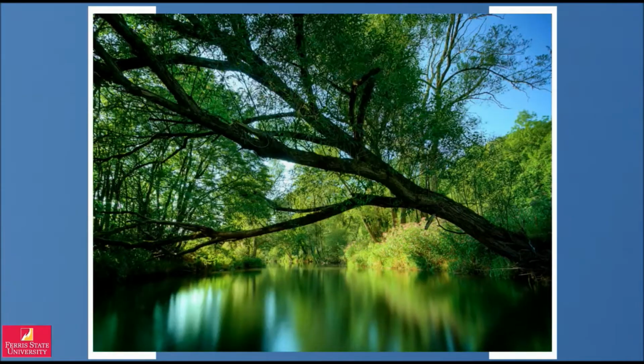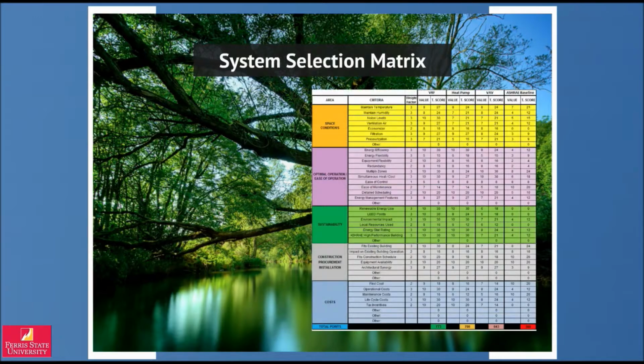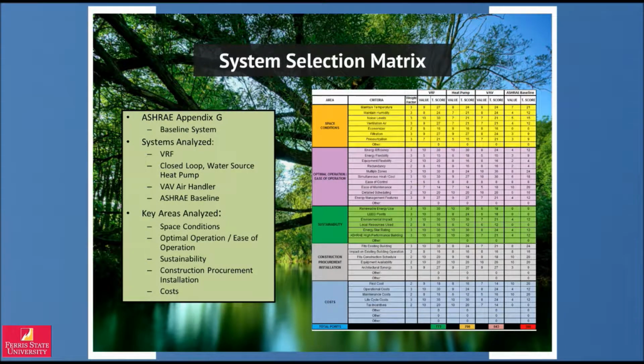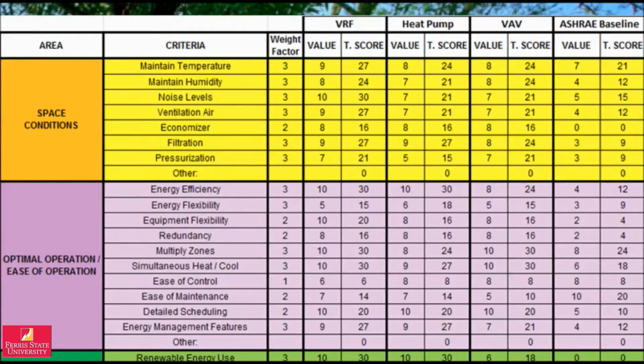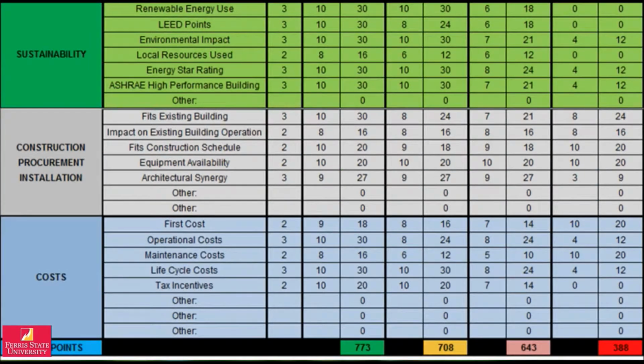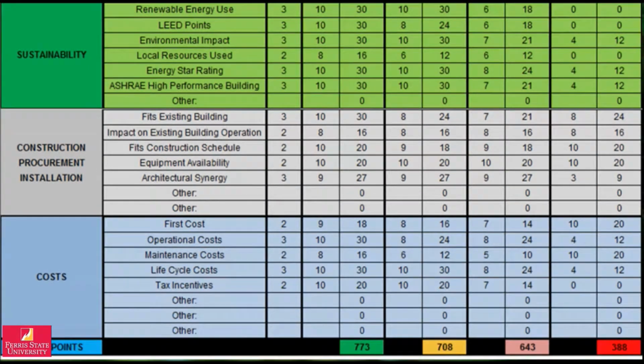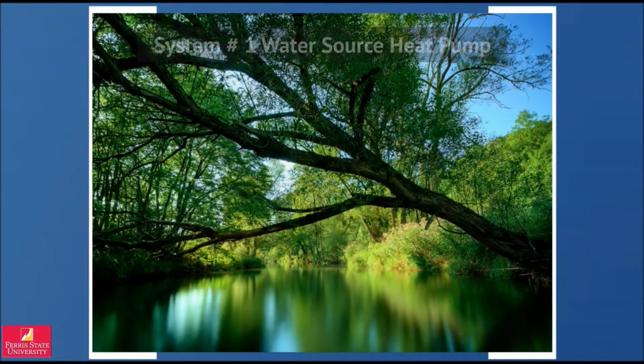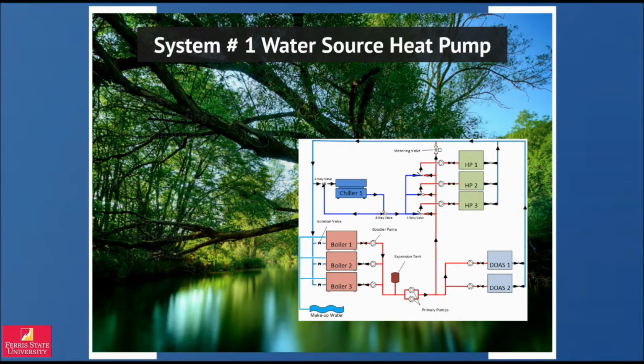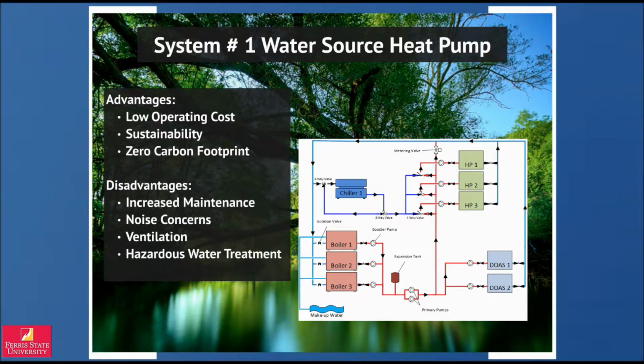From there, 3 HVAC systems were selected for comparison against the ASHRAE Appendix G baseline system through the use of a selection matrix. The 5 core areas of concern were assigned a point value with a weight factor emphasizing the importance of key criteria of each system. The first system analyzed was the closed-loop water source heat pump system. A major issue for this system is the potential for water leakage over sensitive areas and equipment.